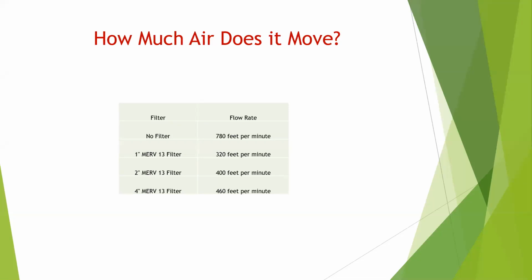Okay. One question from Ron Tuttle is, is 40% outside air enough? Yeah. You know, the ASHRAE recommendations were calling for 100% outside air. We've been doing this for a long time. I've seen very few buildings that can have 100% outside air. The average is about 20% outside air. I would say 40% outside air is wonderful. You know, how much is enough? Nobody knows exactly the answer to that, but it dramatically improves ventilation, and I would say it's a very good step to be able to do 40% outside air.